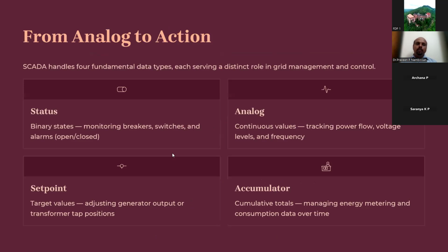The actuation loop. So from analog to action, the SCADA handles four fundamental data types, which are status, analog, set point, and accumulator. Status, in essence, is binary states, monitoring breakers, switches, and alarms. The next is analog, continuous values, tracking power flow, voltage levels, and frequency. And set point, we have some target values. I'll give you a real-time example, then it will be easy to understand how it functions. Then accumulator, cumulative totals, managing energy metering and consumption data over time.